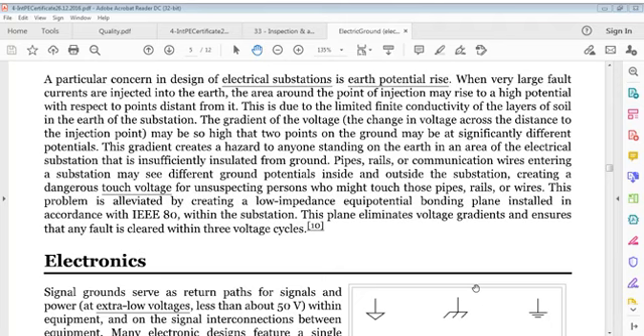This gradient creates a hazard to whosoever is standing on earth in that area of the electrical substation that is insufficiently insulated from ground. Again, the gradient of voltage may be so high that two points on the ground may be at significantly different potentials. Pipes, rails or communication wires entering the substation may see different ground potentials inside and outside the substation, creating a dangerous touch voltage for unsuspecting persons who might touch those pipes, rails or wires.